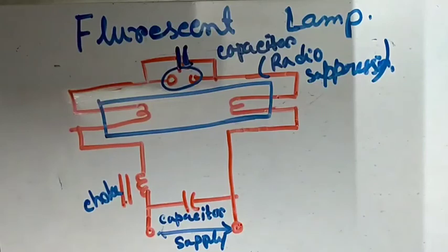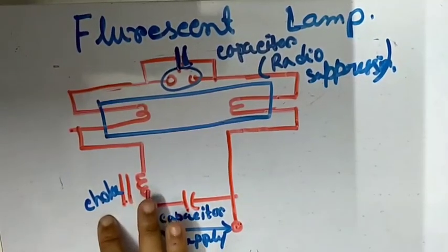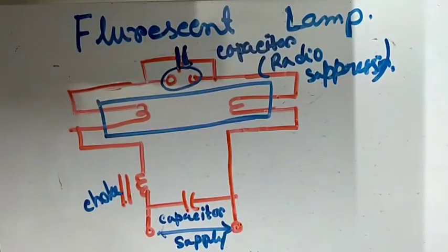When the supply is switched on, the starter provides a path through the electrodes, and the choke is used to provide preheating. The starter switch then opens automatically, thereby the current is interrupted. Since this heating current reduces to zero instantaneously in the choke circuit, the choke field collapses, which releases stored energy and thus produces a high voltage between the electrodes and causes the pre-ionized tube to strike.